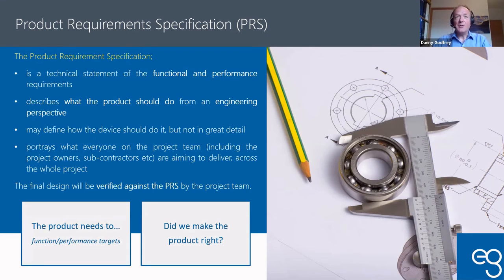And the product requirement specification answers a different question. It doesn't answer whether you made the right product. It answers the question, did we make the product right? Did we make the product that we wrote down that we had to make? So you verify your final design against the product requirement specification. These are things that can be measured, and then you take it back to users and they run a clinical trial and they confirm, they validate, whether you've translated from the user requirements to the product requirements accurately enough, so that when you go from the device back into use, you know you've done the right thing.